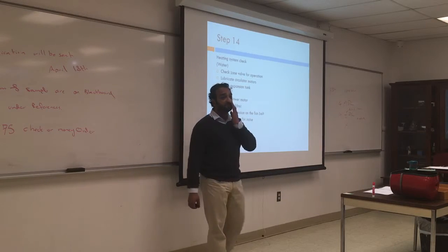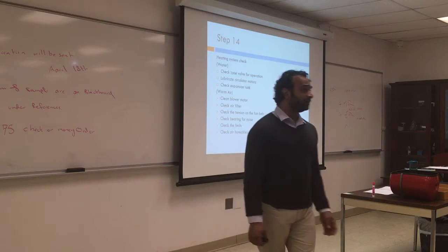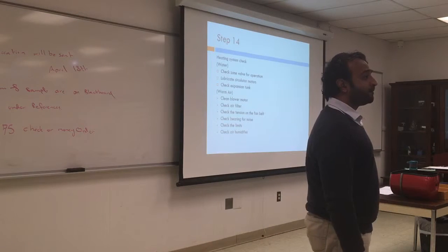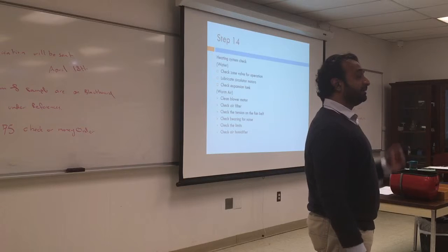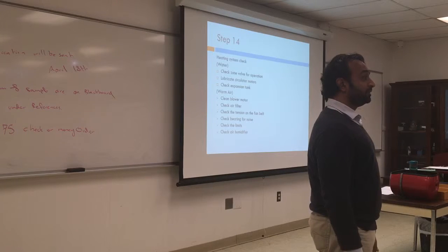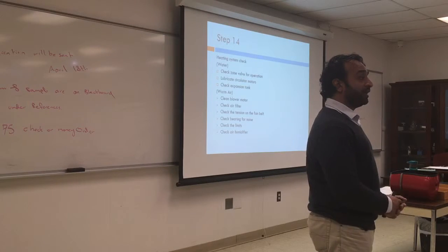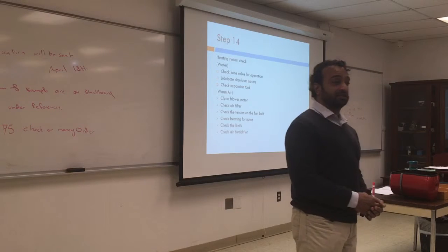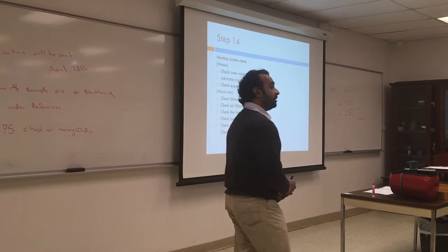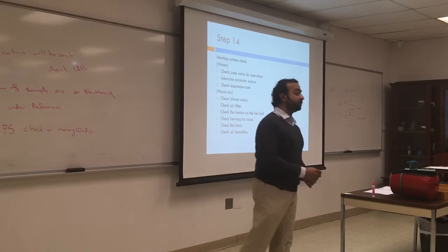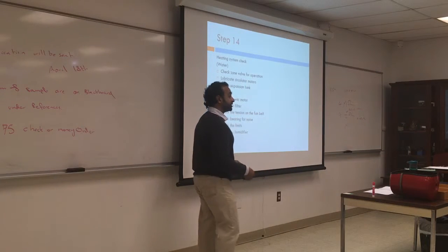Check the limits. How do we check the limits? We did that 3 times so far. You turn it on, set the limit, and make sure it turns off on the limit. So we make sure it trips at the high pressure, make sure the aquastat stops when we reach the water temperature, and make sure that the fan limit switch turns on when the air temperature is correct.